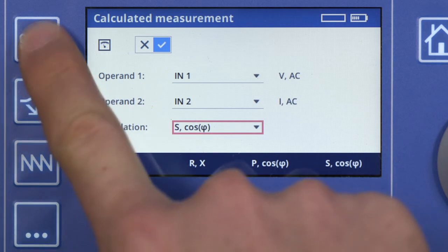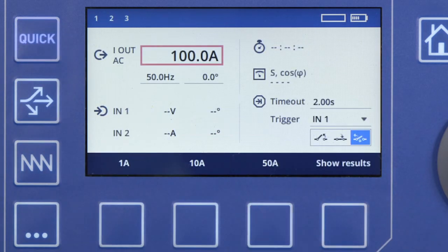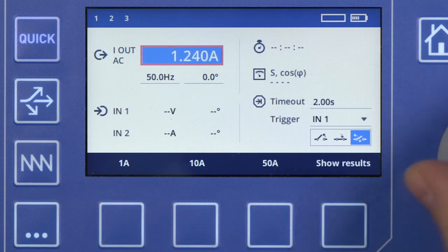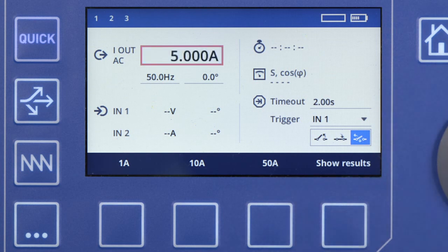In the QUICK app, set a nominal secondary current of 5 amps. Now inject these 5 amps for 2 seconds.